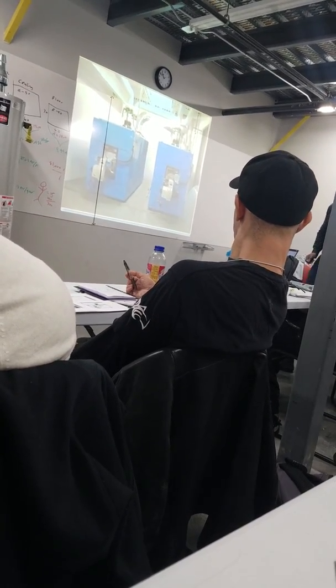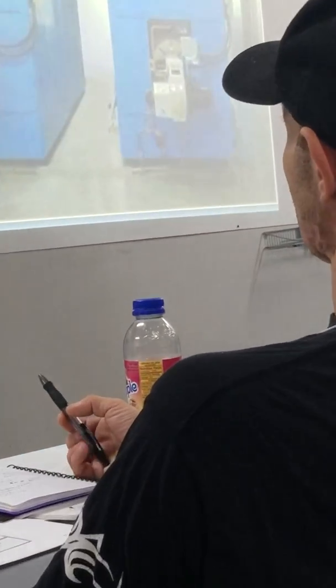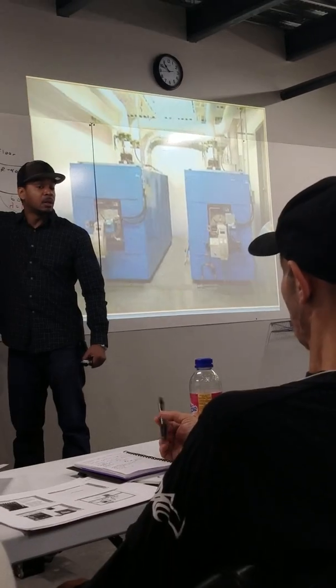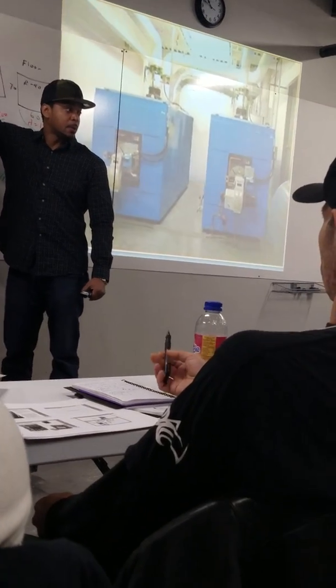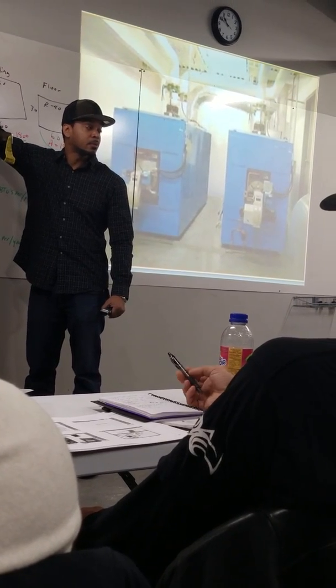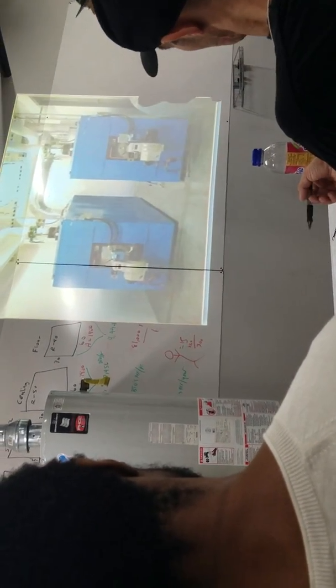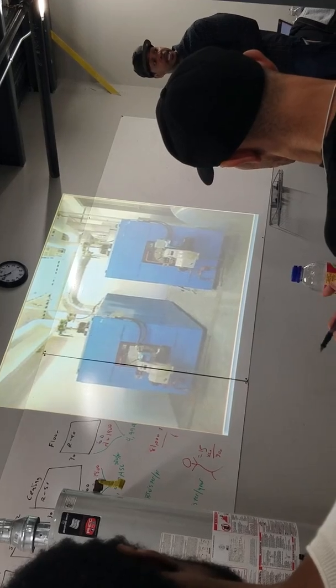Some sealed systems can use this aluminum flue pipe. You put down condensing vented, but you never gave us a definition. Well, we'll get to it. We'll get to condensing and sealed a little bit later. Atmospheric and sealed can still use the same aluminum flue pipe. One is open and one would be attached to a fan or something to induce the draft. In this case, I really can't tell; I have to get a little closer to see. But what I can tell you is that it's a cast iron sectional, oil fired, steam system.